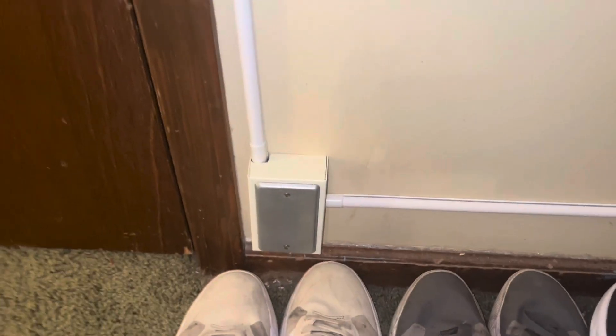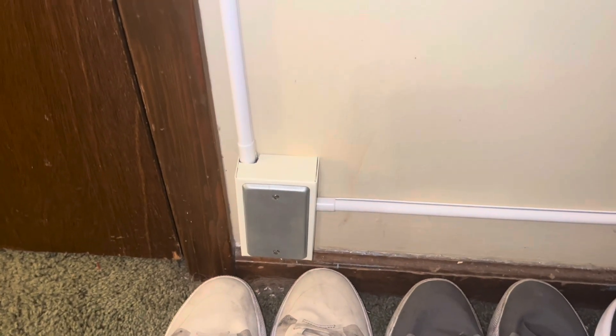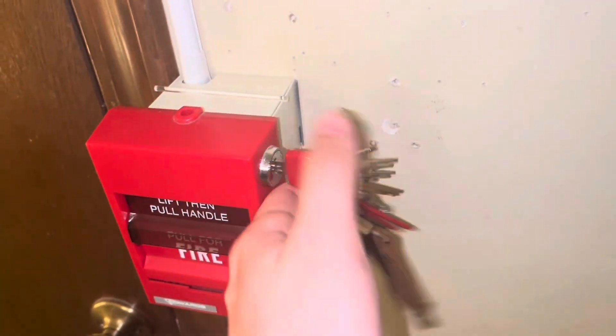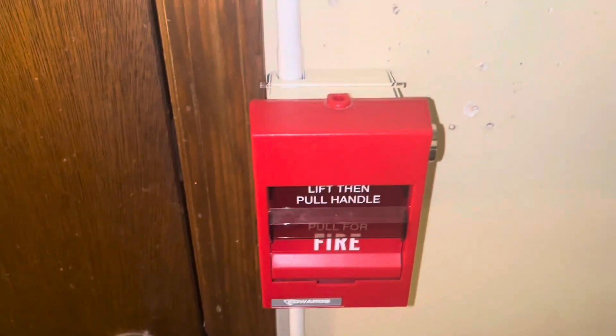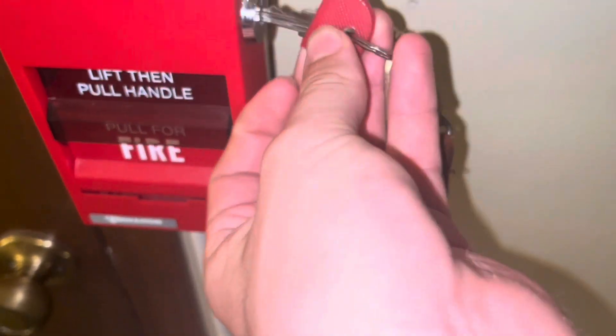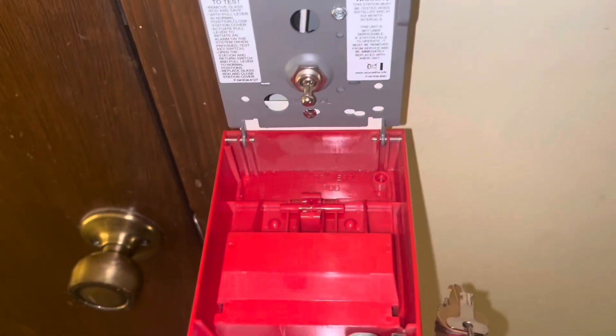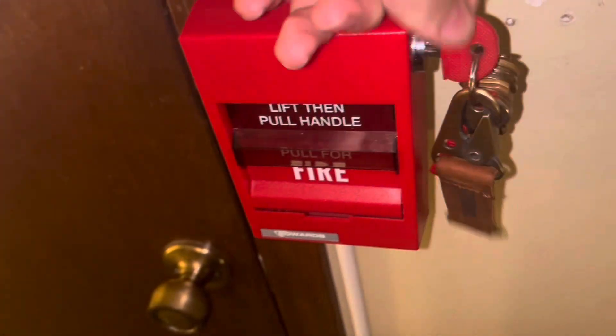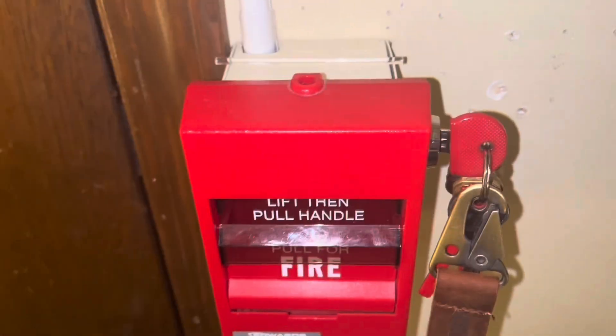I'm not even going to bother opening that box because it's a mess in there. Following this wire mold up, we have an Edwards 278B110 pull station, also known as the SIGA series — though this is a conventional model, not addressable. I have a break rod up there because I took it out since I want to pull the pull station to test it. I'm not going to break the break rod, although I have another one. I might break that one for another test, but for now I'm not going to break any brake rods.